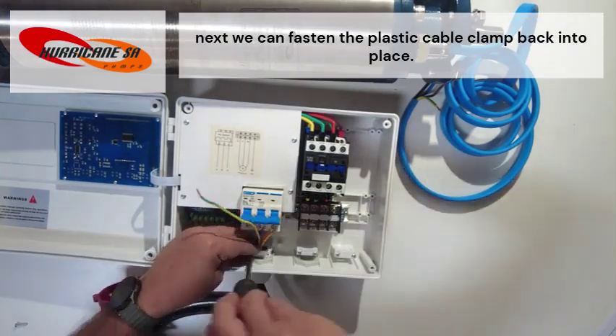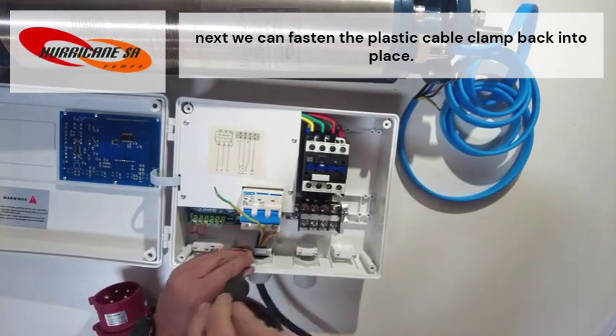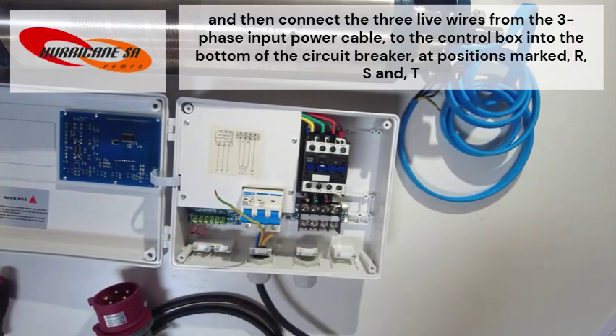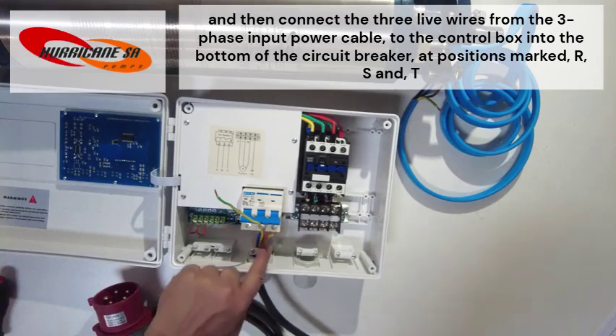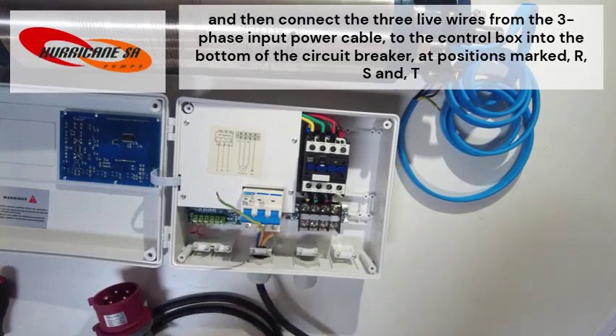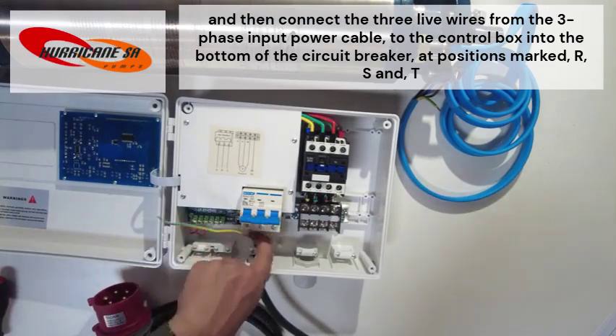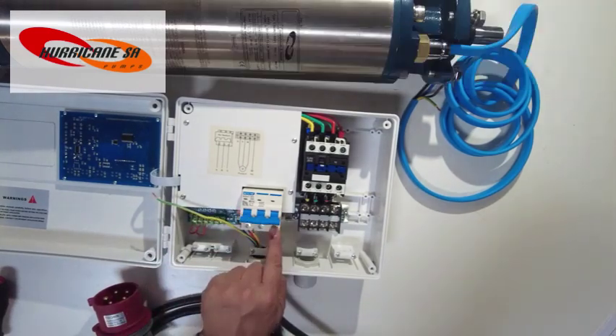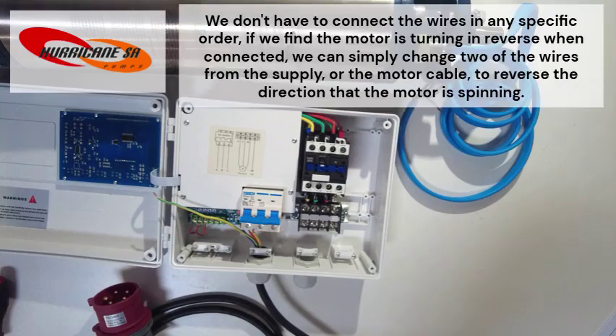Next, we can fasten the plastic cable clamp back into place, and then connect the 3 live wires from the 3-phase input power cable to the control box into the bottom of the circuit breaker at positions marked R, S, and T. We don't have to connect the wires in any specific order. If we find the motor is turning in reverse when connected, we can simply change 2 of the wires in the supply or the motor cable to reverse the direction that the motor is spinning.